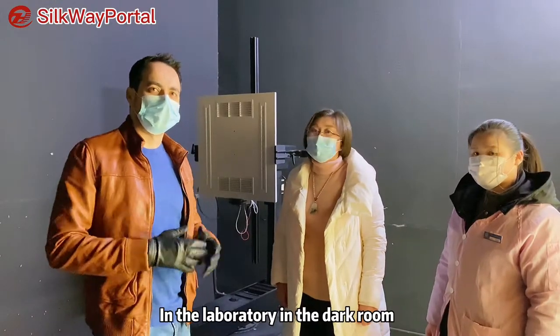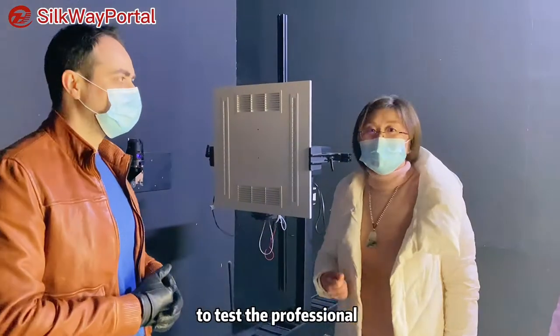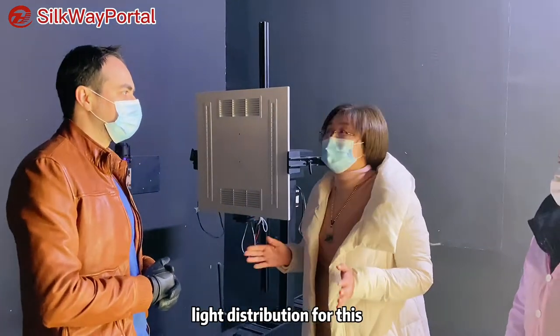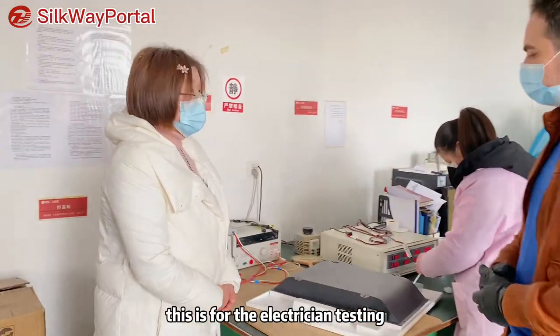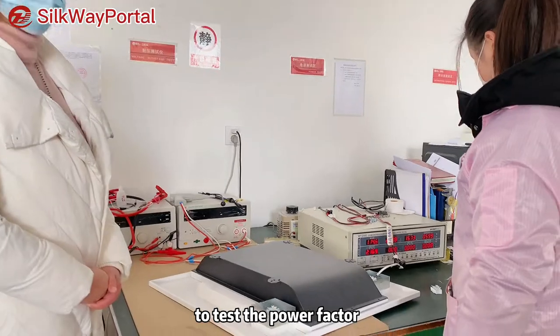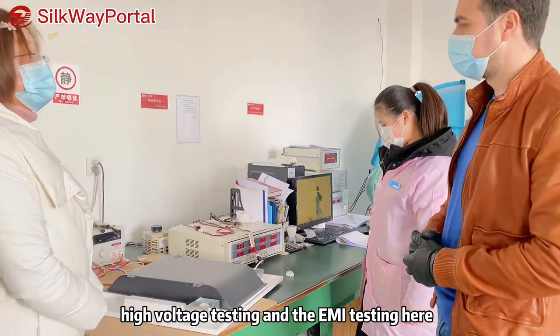Now we are in the dark room. We are using this to test the professional light distribution for these lighting parts. And over here, this is for electrical testing — we test the power factor, the high voltage, and the EMI testing.